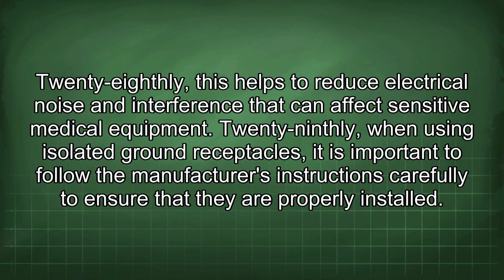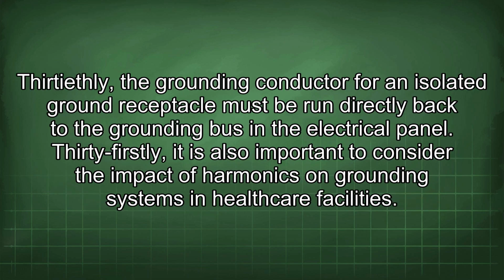28thly, this helps to reduce electrical noise and interference that can affect sensitive medical equipment. 29thly, when using isolated ground receptacles, it is important to follow the manufacturer's instructions carefully to ensure that they are properly installed.